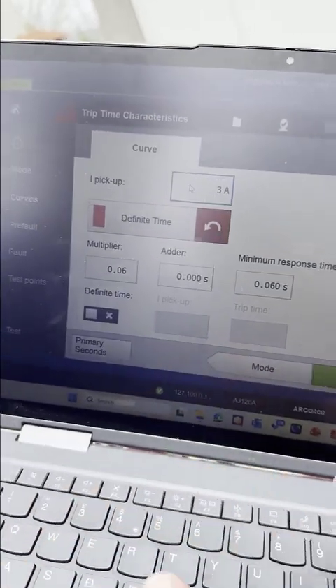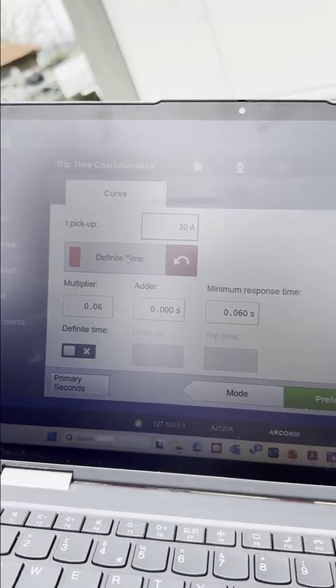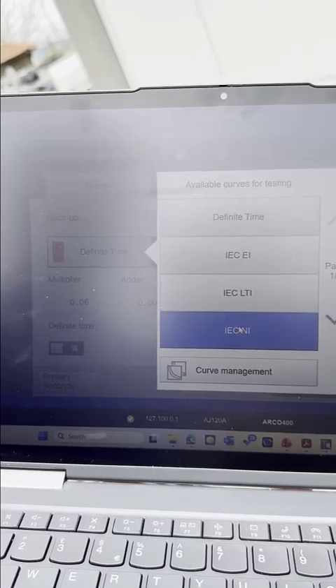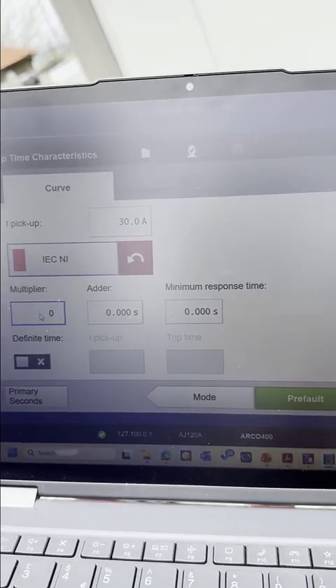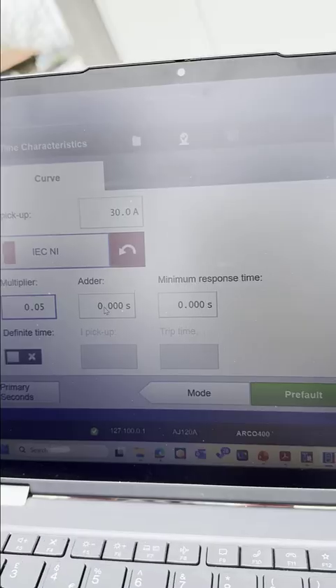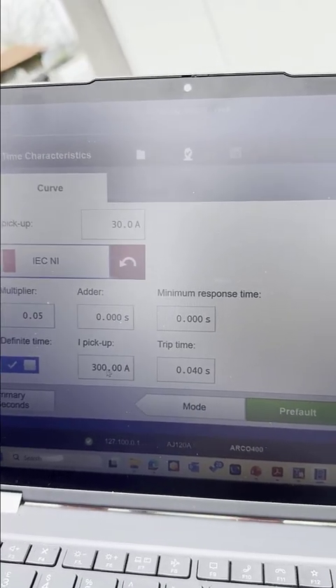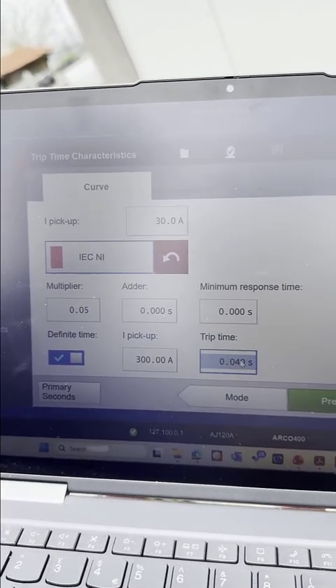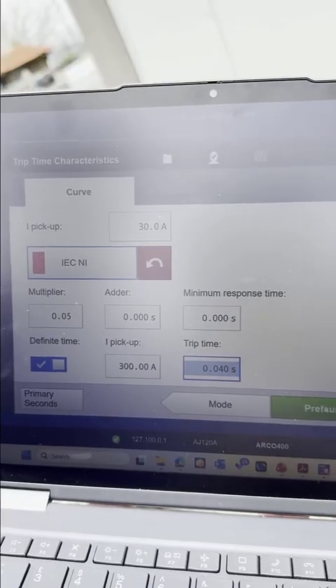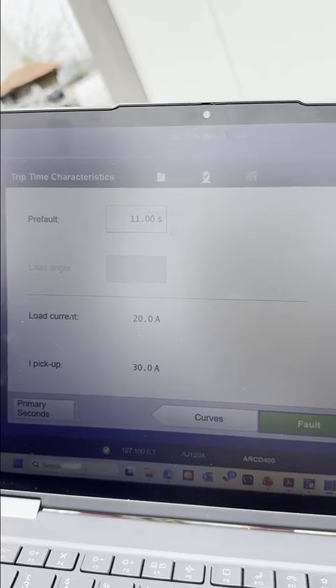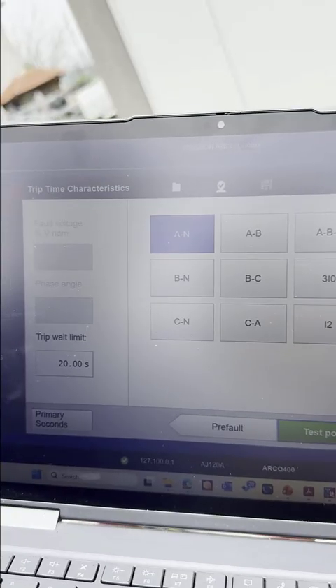You can get back again to change the setting to be overcurrent. Now we are expecting the pickup to be at 30 ampere, and we have the curve is IEC normal inverse, and the time multiplier is 0.05. As you can see, and we have second stage, which is a definite time at 300 ampere, and the trip time is 40 millisecond. Then you can go for the pre-fault. Also the pre-fault time is 11 seconds again. Then you can go for the fault.